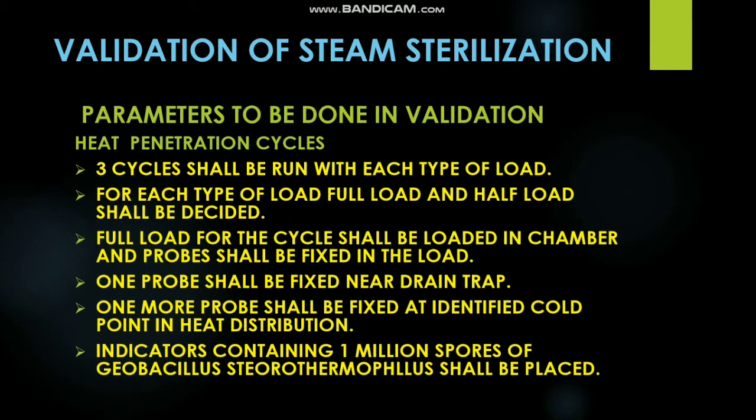Then second comes heat penetration cycles. In heat penetration cycles, first we need to decide what our types of loads are. We can have porous load, like your garments. So if garments have to be sterilized, that is porous load. If your tanks are going to be sterilized, or if terminal sterilization vials are going to be sterilized, that is solid load. So there we can use vacuum also.